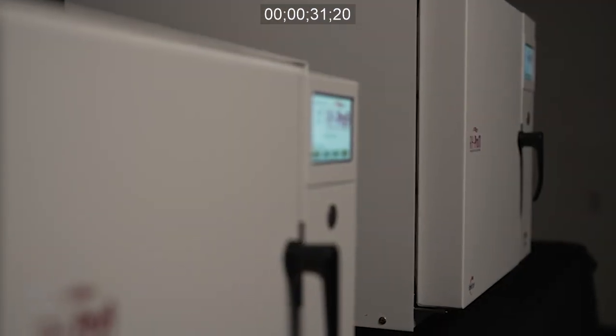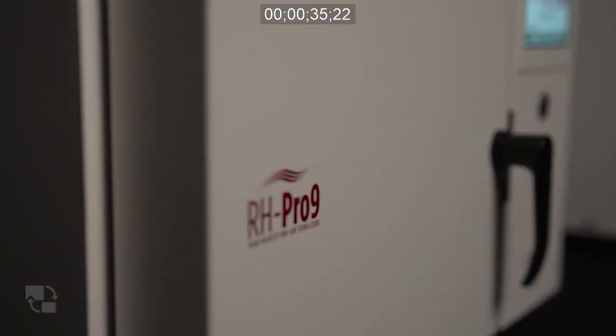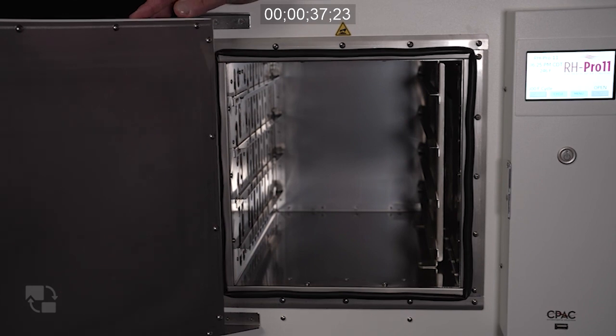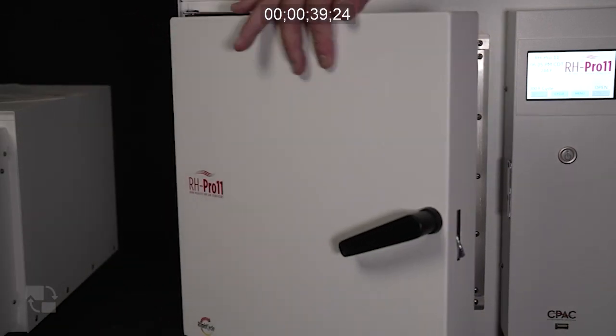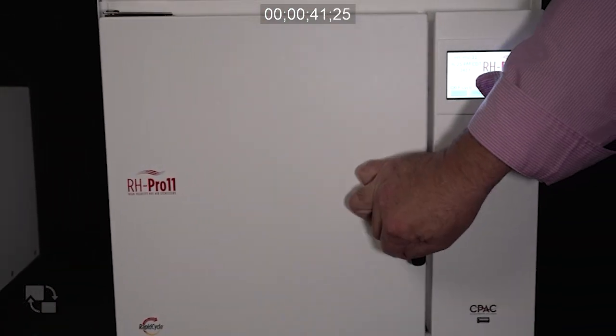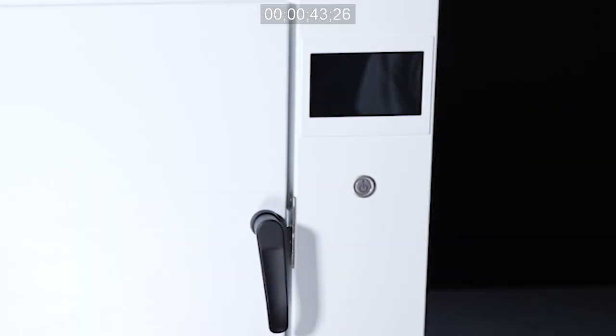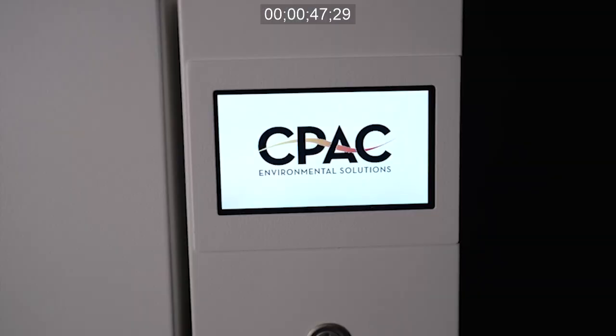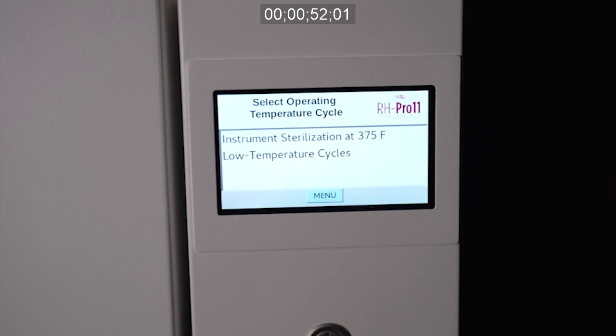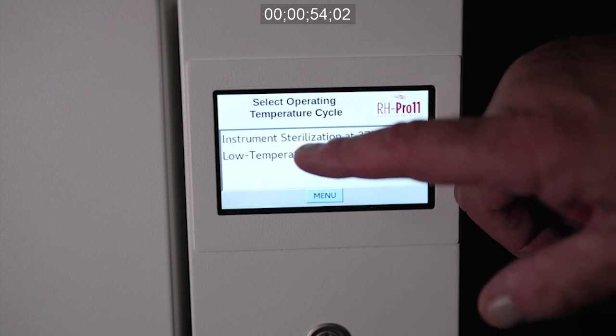Before initiating the process of sterilizing instruments from a cold start, a preheating cycle must be completed in an empty rapid heat sterilizer chamber. To start the preheating cycle, close and lock the chamber door on an empty chamber, and press the on/standby LED button. After an initial startup display screen, the Select Operating Temperature Cycle touchscreen display will appear.